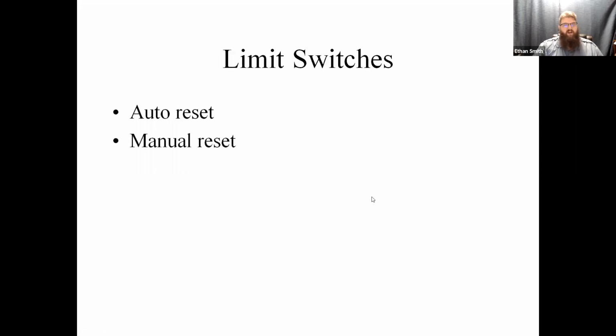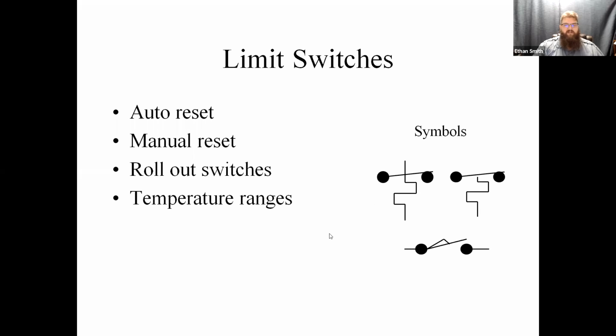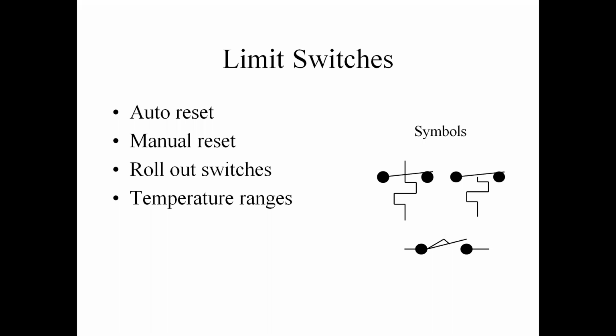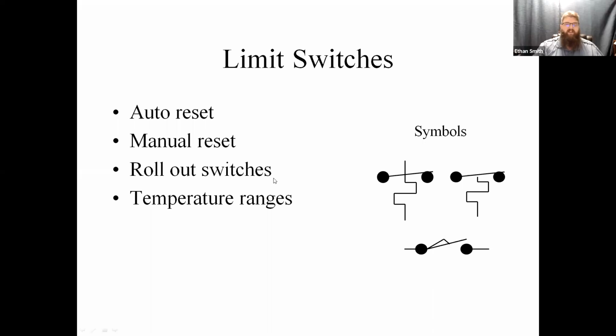Okay. Limit switches come in lots of varieties. Auto reset, manual reset, rollout switches, temperature range switches. Okay, lots of them out there. We got various symbols for them. Which one of those is the manual reset, guys? Little stick at the top left. Top left one, because you got that little stick. That's kind of the dead giveaway on any kind of safety or overload or switch that it's a manual reset. It's going to have that button depicted there. So these are both open on rise temperature switches. This one would be a close on a drop in temperature switch here. Okay.